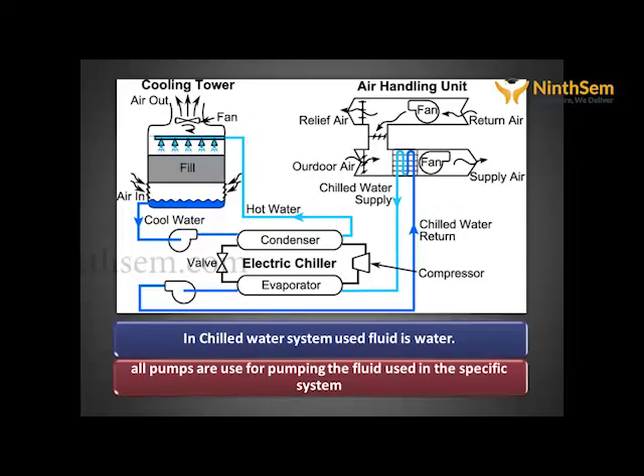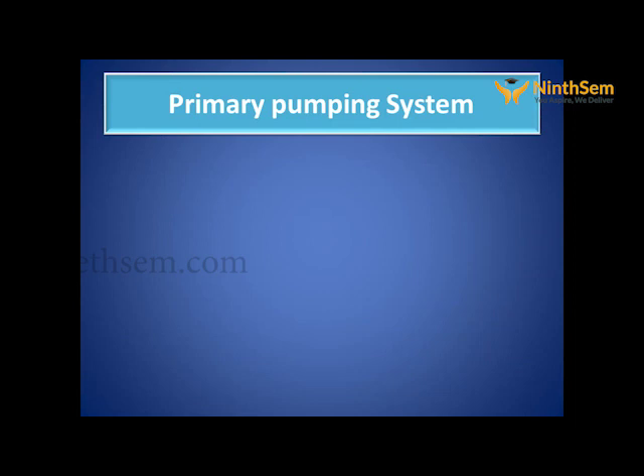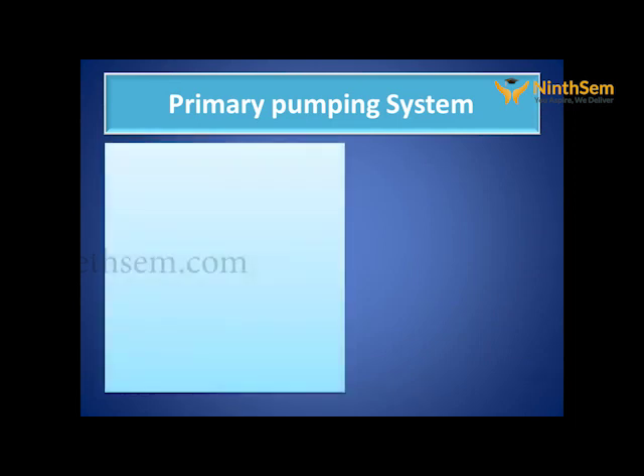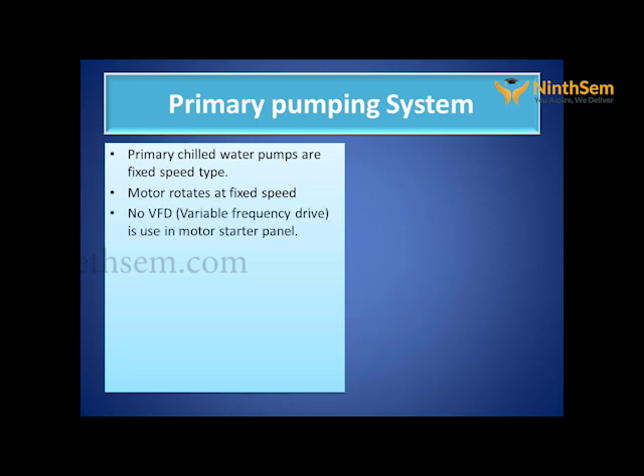In chill water circuit, basically two types of pumping system are involved. Number one, primary chill water system. Number two, secondary chill water system. In most of the cases, primary chill water pumps are fixed speed type. That means motor rotates at fixed speed. No VFD, that is variable frequency drive, is used in motor starter panel, because variable primary chill water system balancing is more complicated than fixed speed type.